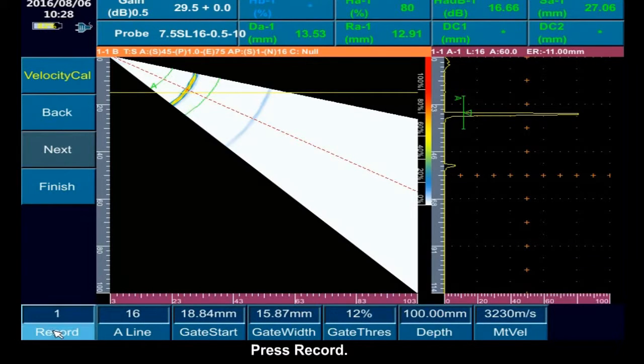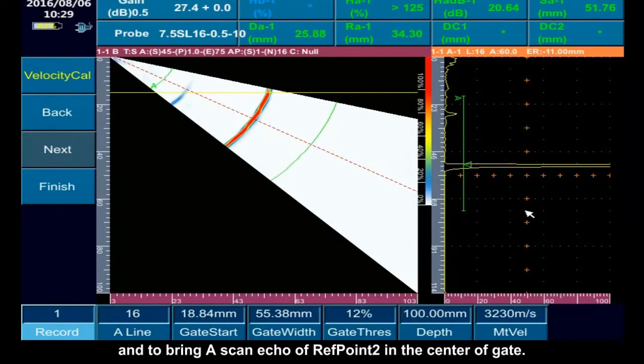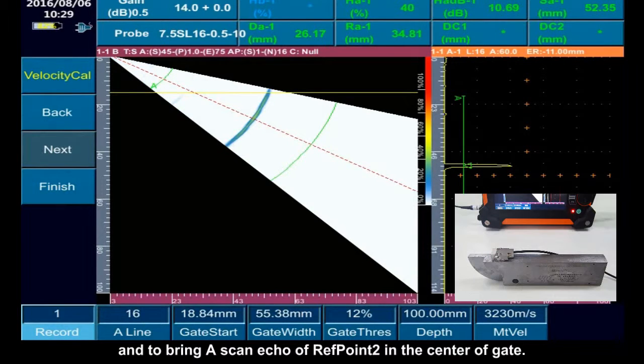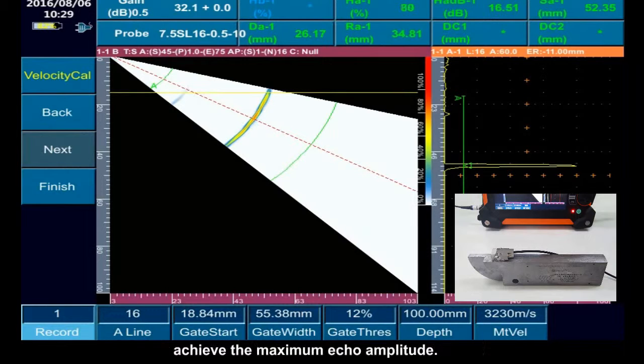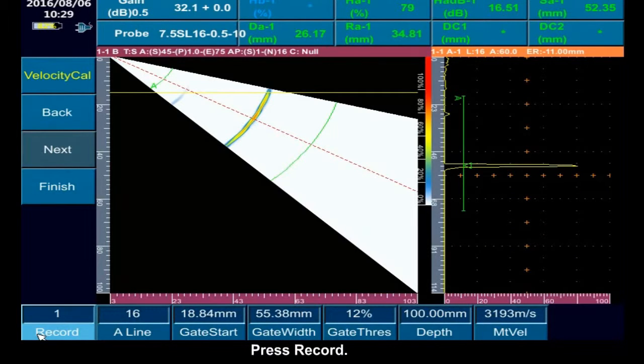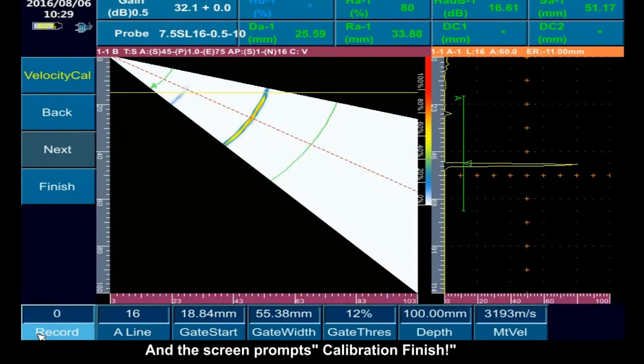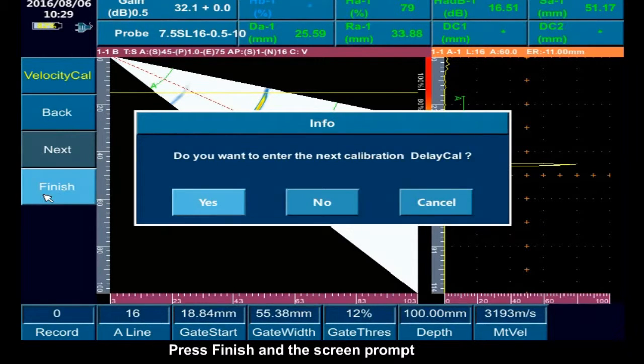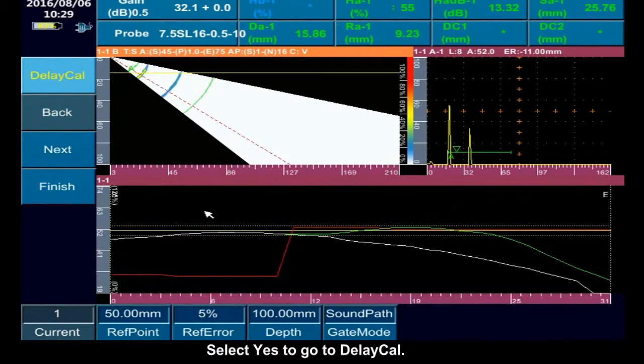Press Record, and bring the scan echo of reference point 2 to the center of the gate. Move the probe back and forth to enable reference point 2 to achieve the maximum echo amplitude. Press Record, and the screen prompts Calibration Finish. Press Finish and the screen prompts, do you want to enter the next calibration, delay calibration? Select Yes to go to delay calibration.